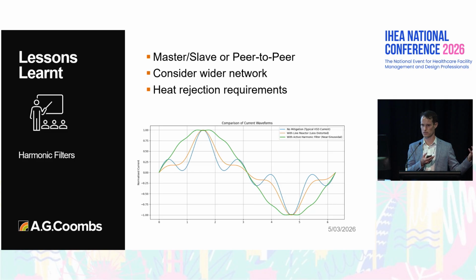So by providing these filters on the MSSBs, we're not only dealing with potential chiller harmonics, we're also looking at EC fans and any other VSDs on the network. It also allows you to select what make and model of filter you're using, so that you can roll it out across different parts of the hospital. So yeah, lots of benefits to that, but I wanted to illustrate the impact. The blue line is a typical unfiltered supply from a VSD. If you add a line reactor, you get the orange line, which is a little bit better. But the green line is what we're really chasing, more sinusoidal, less noise. So that's the impact of these types of devices.